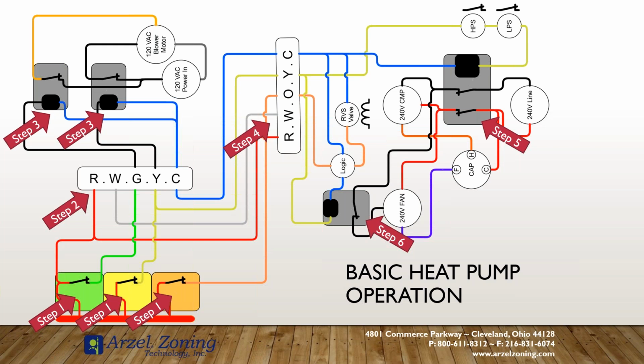And as we start testing for the voltage, we can start to knock things down to see where the problem's at. If our compressor and our outdoor fan or our condensing fan motor don't start, it might be a high pressure switch, it might be a low pressure switch that's open. Once we verify those switches, then we can move on to figuring out where the problem's at. So the defrost board applies some logic to it. That logic is going to determine whether we're running in heating or cooling based on what's coming into it.